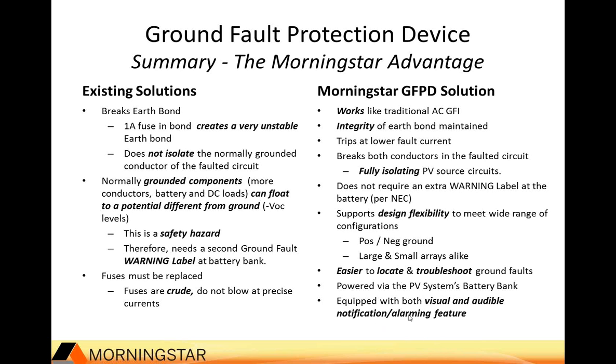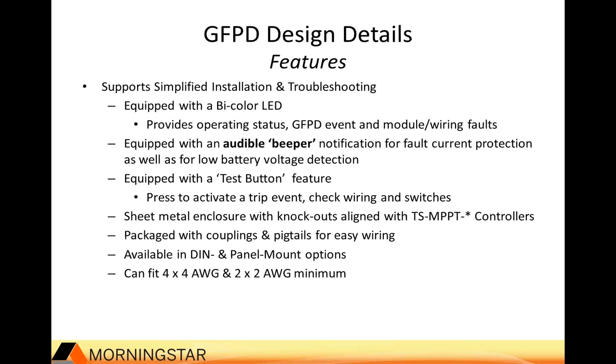And our indicator has both visual and audible electronic notifications, so there's a little more clear idea of what's happened with the system. So we have a bicolor LED that gives you current status. We have an audible beeper. There's a test button to put the system through a test and trip the breakers to make sure that everything is functioning okay.